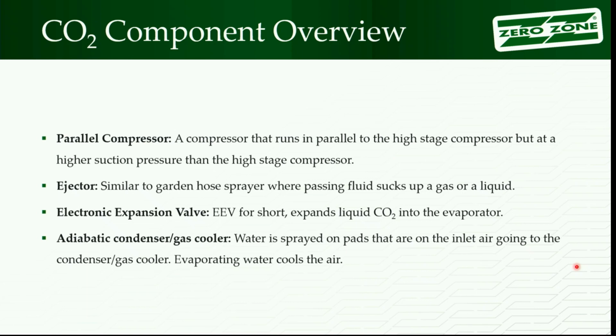And the advantage then, of course, is trying to stay out of transcritical mode. So you have all these days where maybe it'd be transcritical. There's an energy penalty when you hit that transcritical. You take that step, and it's a big step. Stay below it, you can save some energy. So state of California, I think code requires like half your climate zones can't just be air cooled. You have to have water cooled with that, or typically I'm going to wind up adiabatic.